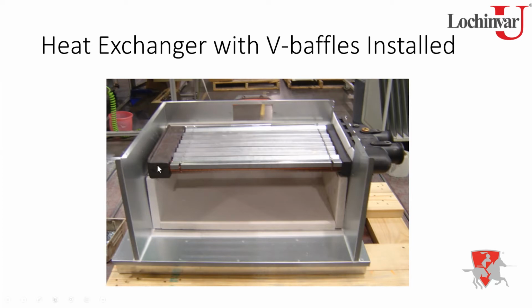The rear header back here, though, is allowed to float. So it's not attached to anything, because you're going to deal with expansion and contraction as this thing heats up and cools down. That rear header is allowed to float around a little bit, so you're not going to attach or secure that with anything. Now here we're looking at a completed heat exchanger installed in the unit. At this point, we've added our V baffles across the top of the heat exchanger. The whole point behind the V-baffle is to slow the flue gases down a little bit, to allow them to be forced through the fins of the copper tube to give you better heat transfer.